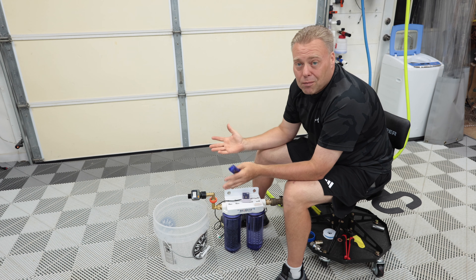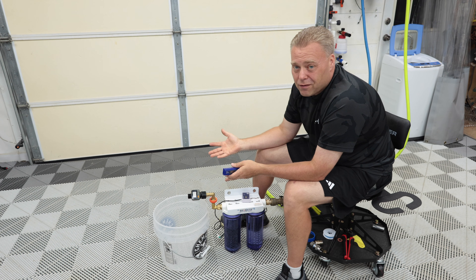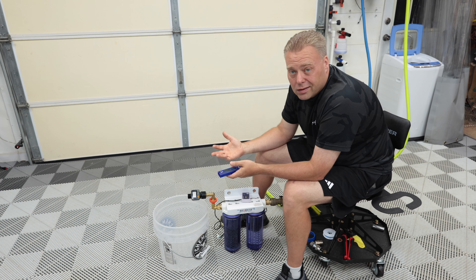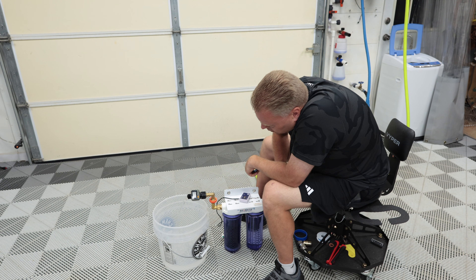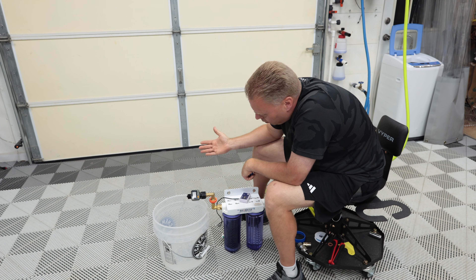Not that anything above 5 ppm isn't spotless, but if you're using a system like this, when you start hitting 5 ppm that's when you order your refill. Hopefully by the next time you run you'll be at about 10 — I wouldn't go much more than 10. Flow is sticking right at about 1.51 to 1.58 like before, about 6 gallons right now.